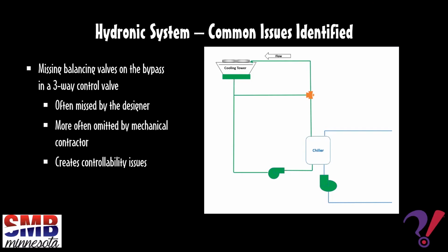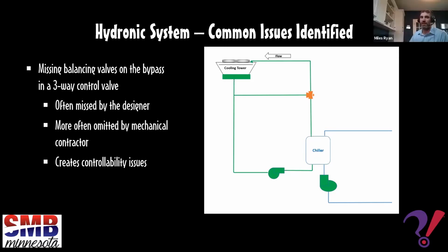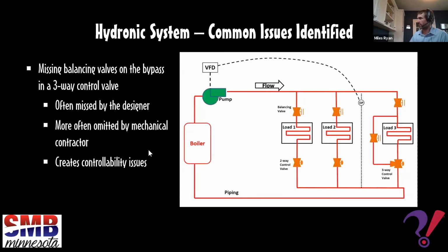Okay, this one's from the person that asked the bypassing balancing valve question. They're asking, is the balancing valve in the bypass also required in chilled water systems? Yes, if you're talking at a coil, like in this scenario right here, if this was all blue pipe and this is a chilled water system with a chiller and cooling coils, you'd often see one or a couple of three-way control valves with an associated bypass pipe, and the exact same concept applies there. You would have a balancing valve on that to make sure you're always meeting minimum flow requirements for the system.